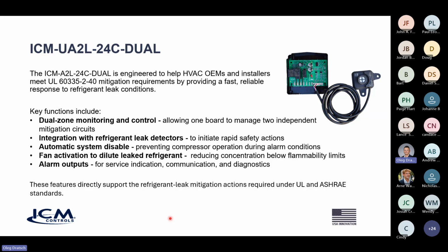So what it does, as I mentioned before, when it senses a leak, it's able to shut the compressor off. And again, the reason for that is a spark in the compressor could potentially ignite an A2L refrigerant leak. So shutting the compressor off is very, very important. And then it's also able to activate the fan. And so what the fan activation does is it expels any type of A2L refrigerant in the system. So this reduces the concentration below the flammability limits. There's also alarm outputs in terms of a flashing light that will tell you when an alarm condition is underway.